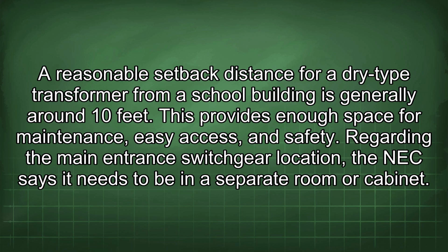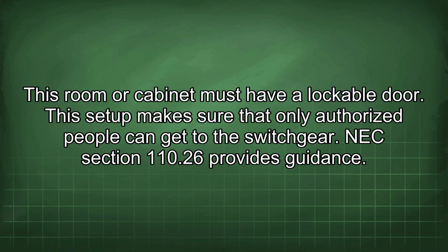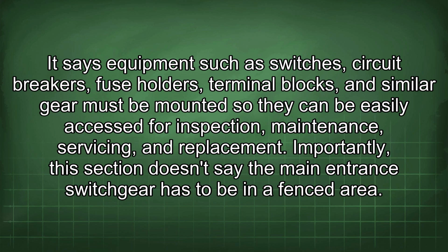Regarding the main entrance switchgear location, the NEC says it needs to be in a separate room or cabinet. This room or cabinet must have a lockable door. This setup makes sure that only authorized people can get to the switchgear. NEC Section 110.26 provides guidance. It says equipment such as switches, circuit breakers, fuse holders, terminal blocks, and similar gear must be mounted so they can be easily accessed for inspection, maintenance, servicing, and replacement.